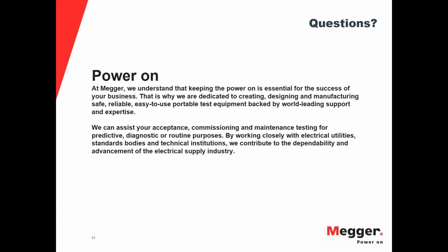The temperature of the capacity test is the temperature of the electrolyte, not the ambient, correct? Yes, that's true. So you need to look at the temperature of the cells. Under normal operation, the temperature of the batteries will pretty much be the same as the temperature of the room, but as the battery discharges during the process, the batteries might get a little warmer. So yes, an accurate way of assessing the batteries is to look at the temperature of the batteries and not just the temperature of the room.